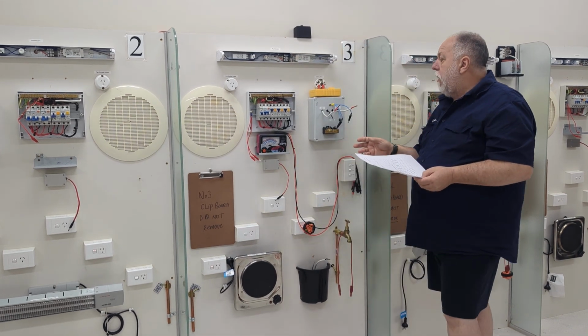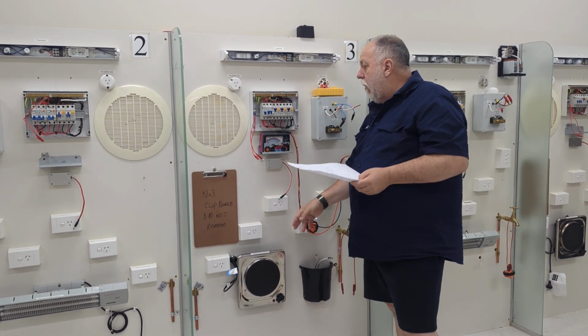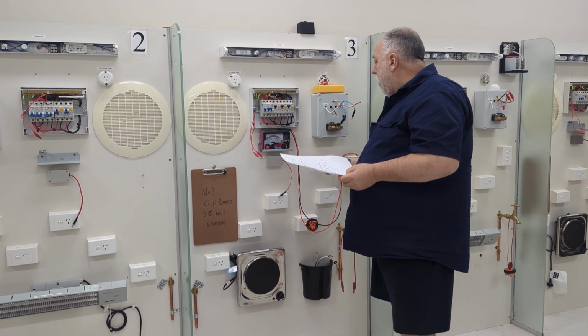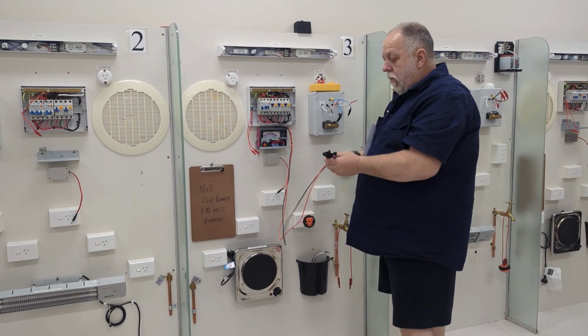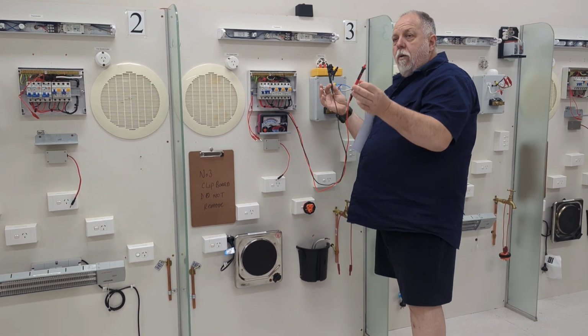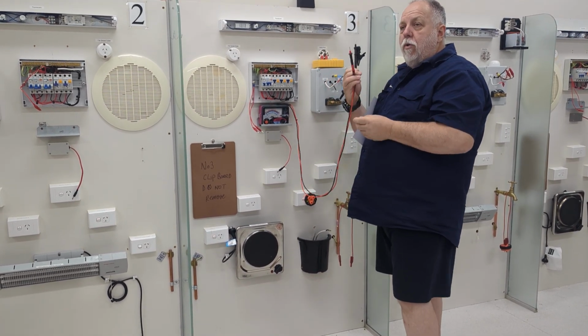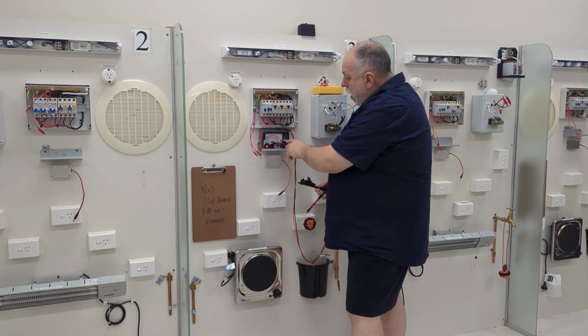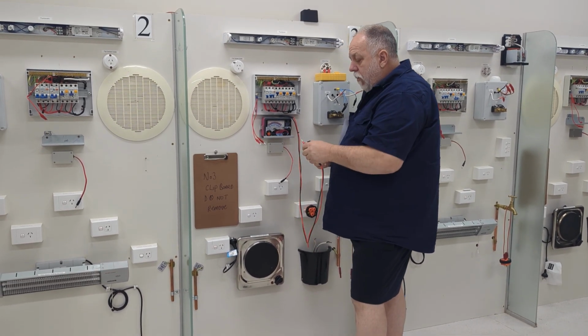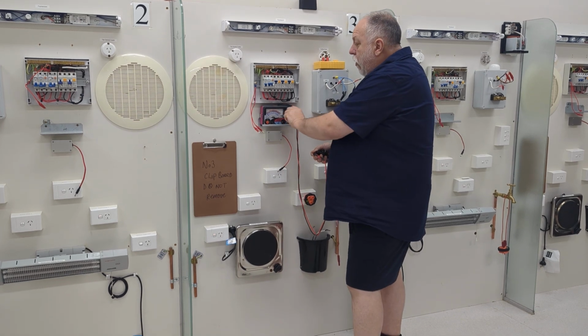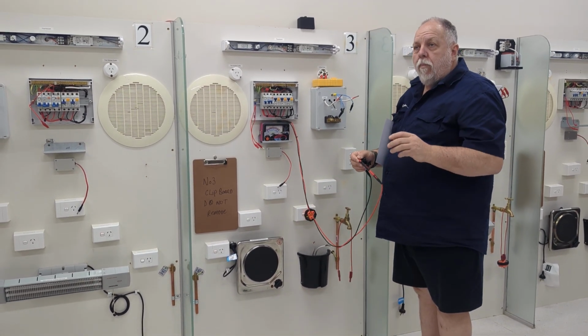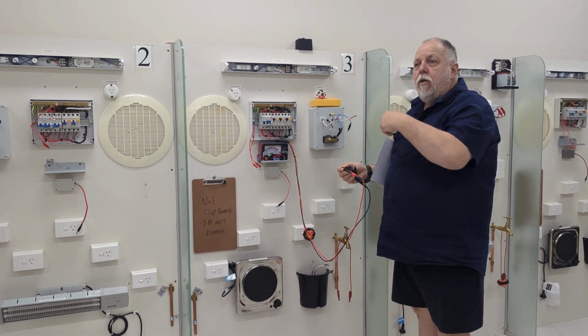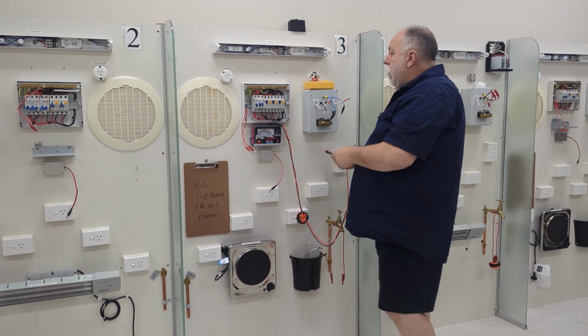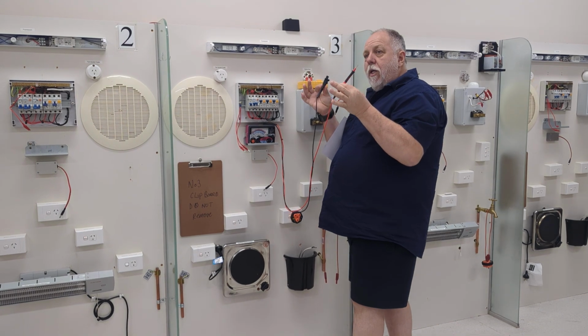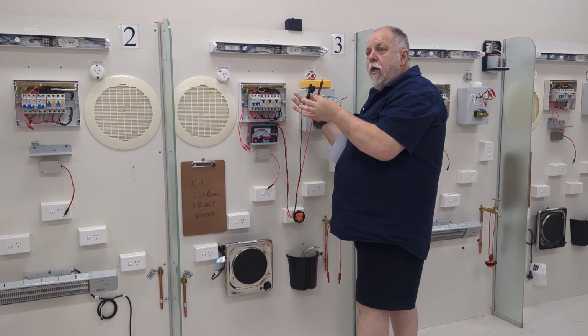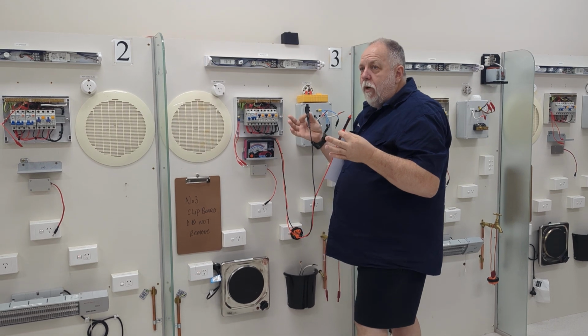Okay? Trailing leads are also used for, for example, testing the main earth, testing the bonding earth all the way around the property. So with a trailing lead, I would have one of these attached to my main earth, and the other one would be a 20-metre lead. The main thing we have to do with that, like the SWP, is zero it out. So we would select that to 3 ohms, join the trailing lead and the other lead together, and we remove that resistance of that lead out. That's all you've got to do. Once you've done that, you go around and take the readings of all your earths. The bottom line is you don't want to be adding the resistance of the leads to your trailing lead to the readings and then being out by 1 ohm or 2 ohms, whatever the resistance is.